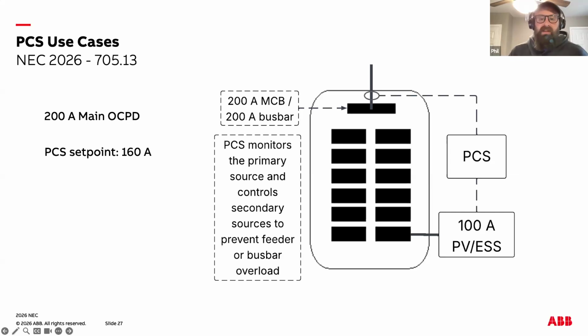This practical benefit is significant. The electrical infrastructure can be used far more efficiently, and system designers can add larger DER systems to existing equipment. Conductor and breaker sizing are based on the PCS set point, which, per Article 120, can be as high as 80% of the main breaker rating, allowing for much larger PV or ESS systems while still maintaining full code compliance.